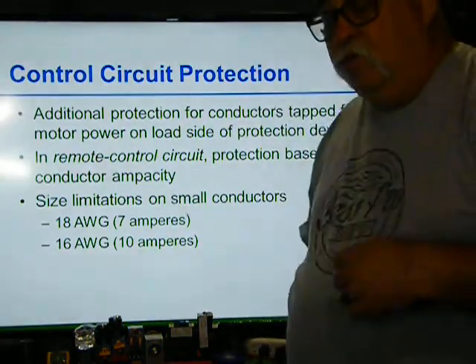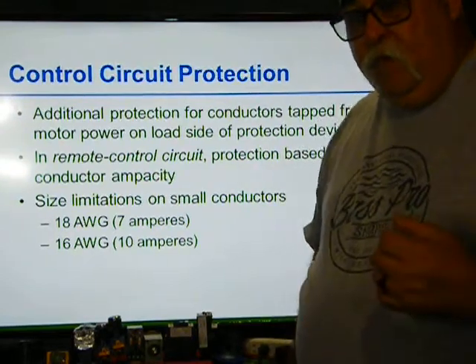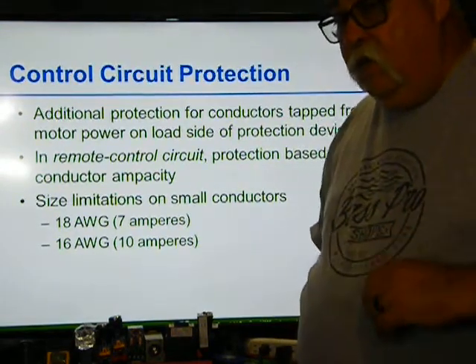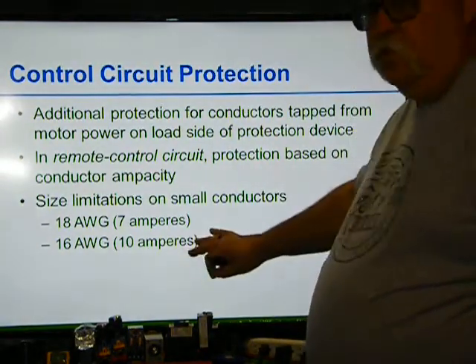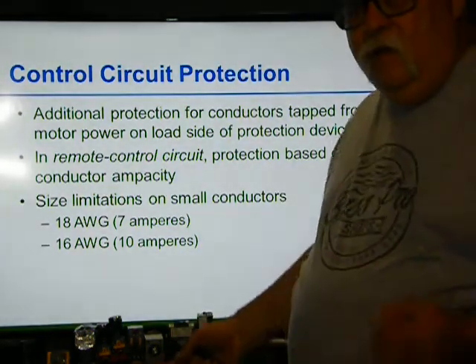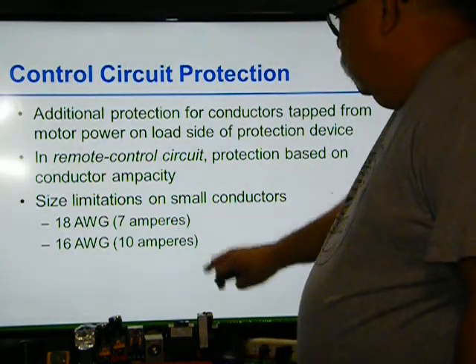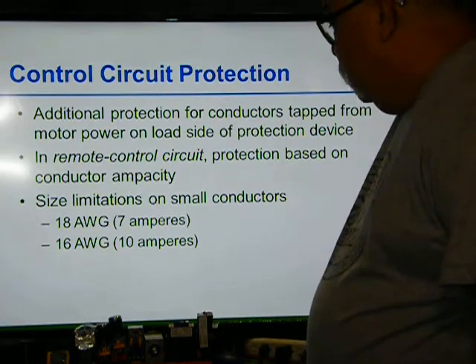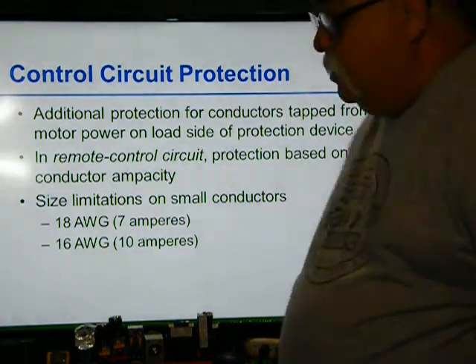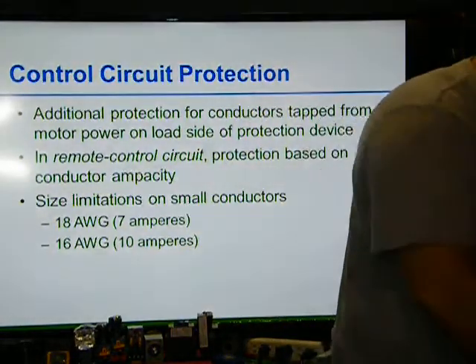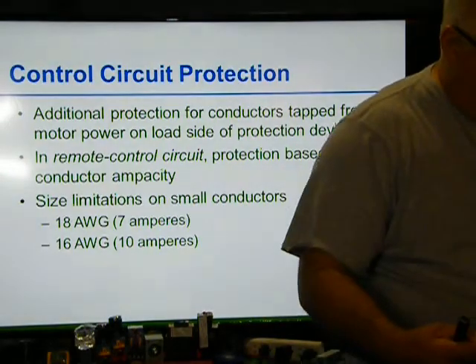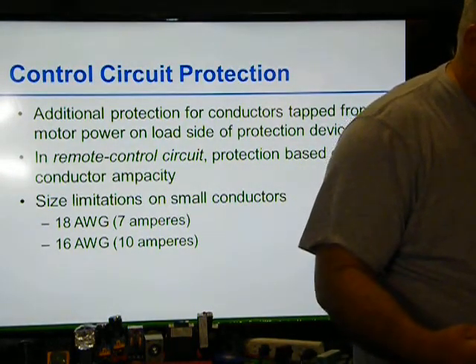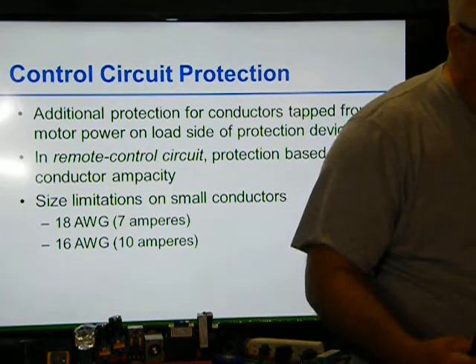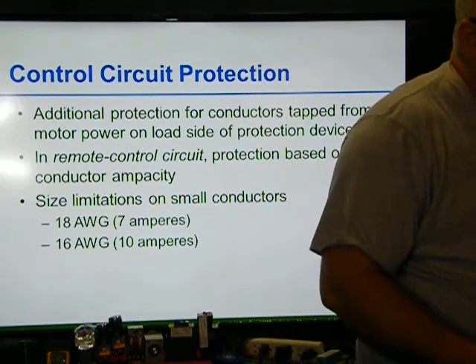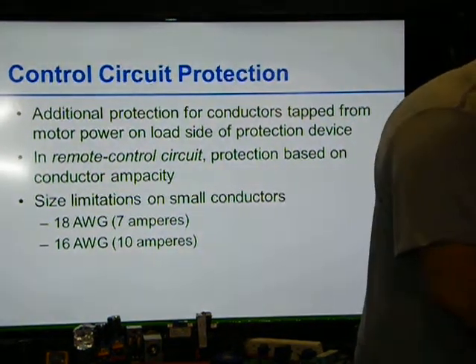Remember, the smallest building wire is a 14, but for controlling things, we can use smaller wires. Why? Because it's only carrying minimal currents. So limitations on small conductors: number 18, 7 amps, and number 16, 10 amps. A separate disconnect can be used for the motor power supply and the control circuit. However, the devices must be adjacent to one another. So you have to be able to turn it off.